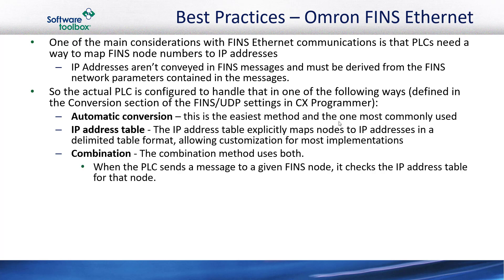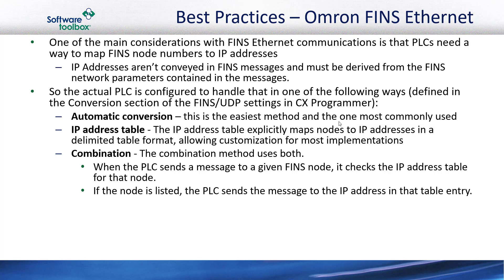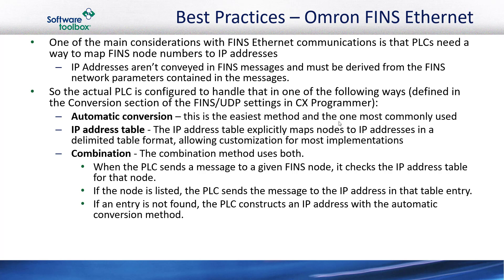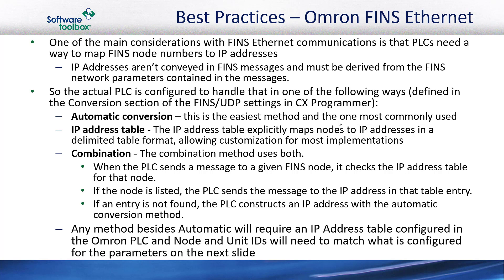When a PLC using the combination method sends a message to a given FINS node, it checks the IP address table for that node. If the node is listed in the IP address table, the PLC sends the message to the IP address in that table entry. If an entry is not found, the PLC constructs the IP address with the automatic conversion method. Any method besides automatic is going to require an IP address table configured in the Omron PLC, and node and unit IDs will need to match what is configured for the parameters on the next slide.